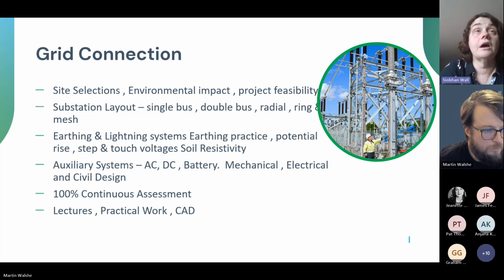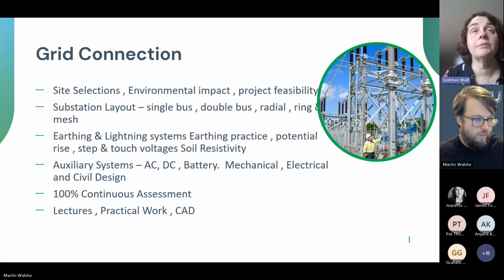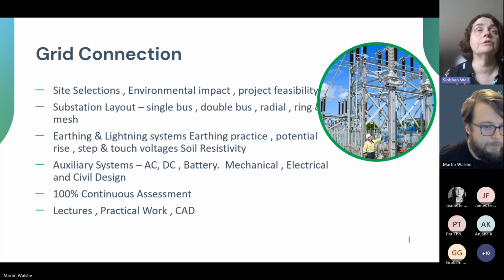We look at how a substation is laid out, the different layout types typically used in Ireland as recommended by EirGrid, such as single bus and double bus. We'll also cover earthing systems and lightning protection, how to lay out an earthing grid, how to conduct soil resistivity tests, and review the auxiliary systems and the mechanical, electrical, and civil design of a substation.